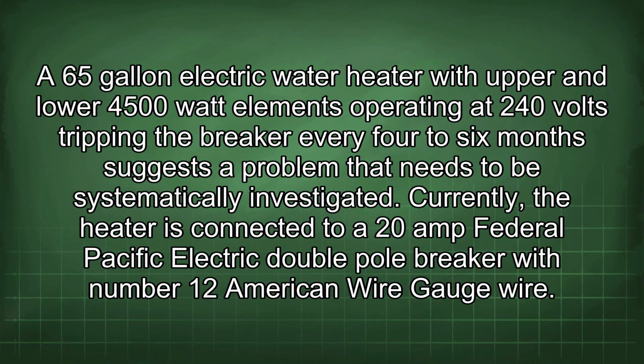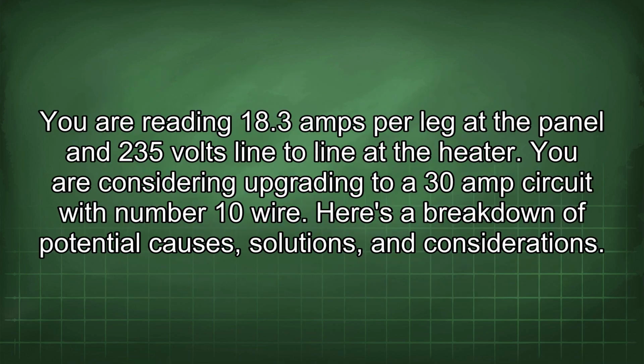A 65-gallon electric water heater with upper and lower 4,500 watt elements operating at 240 volts tripping the breaker every 4 to 6 months suggests a problem that needs to be systematically investigated. Currently, the heater is connected to a 20-amp Federal Pacific Electric double-pole breaker with number 12 American wire gauge wire. You are reading 18.3 amps per leg at the panel and 235 volts line to line at the heater. You are considering upgrading to a 30-amp circuit with number 10 wire.